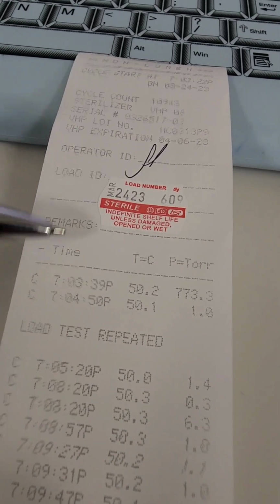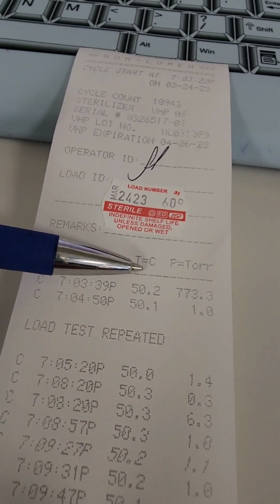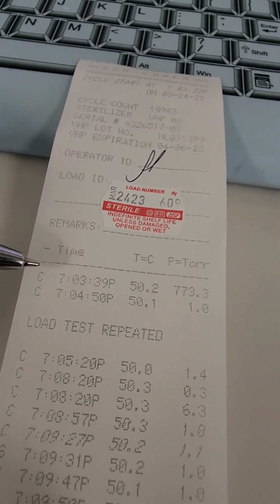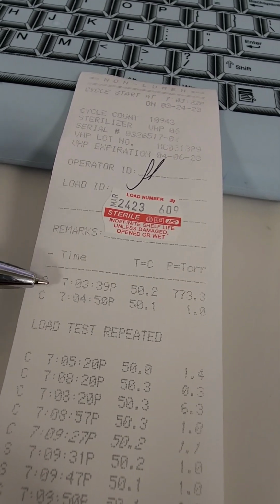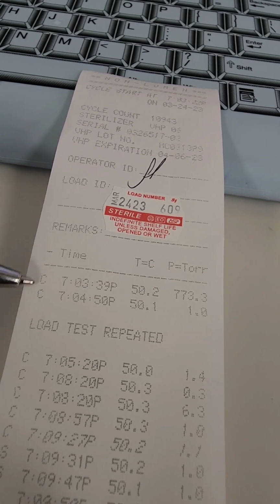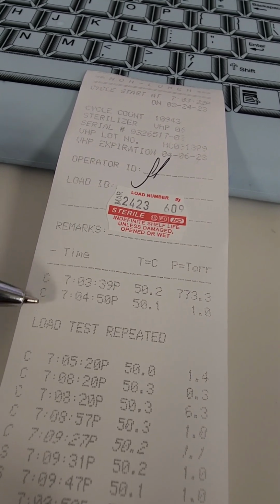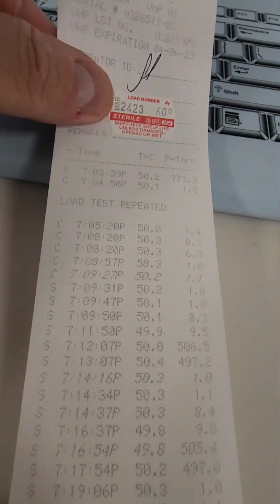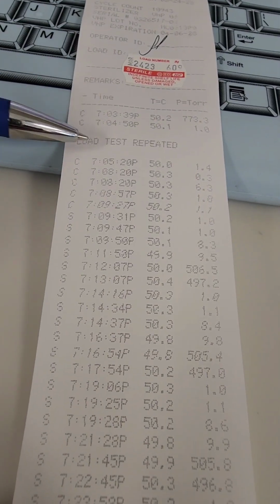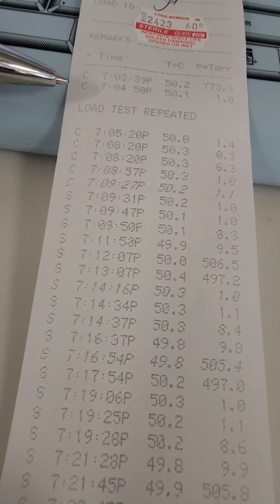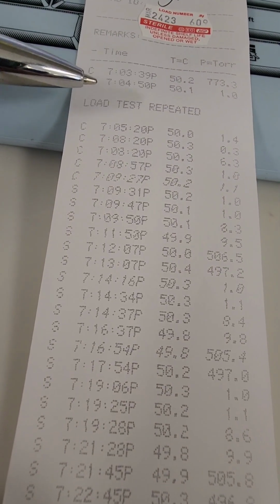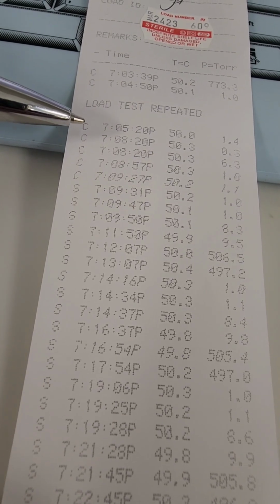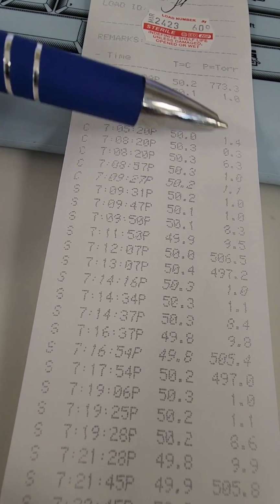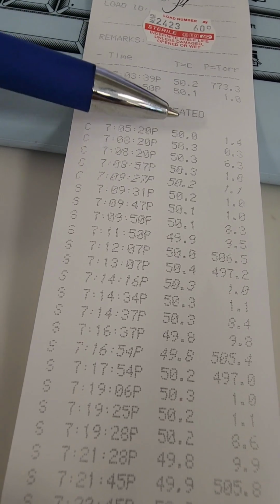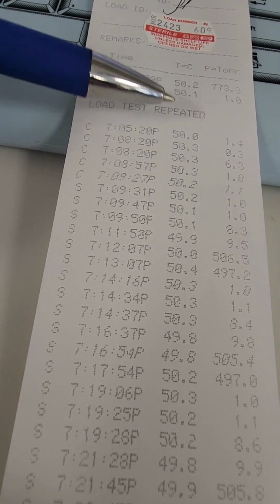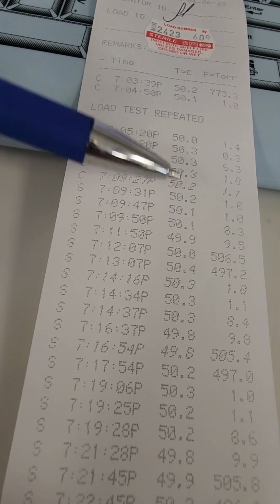All right. The next line is going to show you time, temperature, and pressure. Okay. This is similar to a steam sterilizer. The time it took to sterilize, the temperature at which it should be held, and then the pressure. Now, just like a steam sterilizer, there are certain parameters that need to be met. Okay, you have the conditioning phase where the unit is actually analyzing the package. So if there's a lot of air in that package, if there's some moisture in there, the conditioning phase is getting that package ready for sterilization.